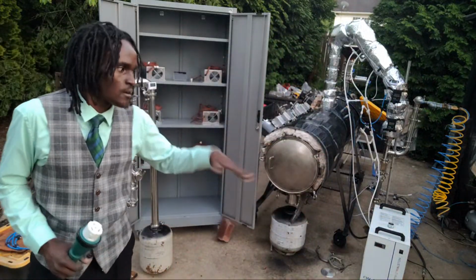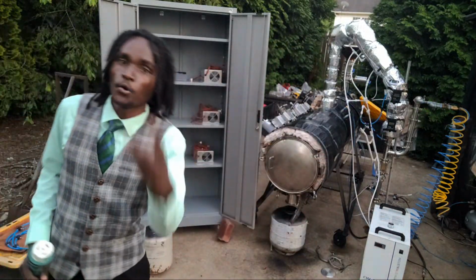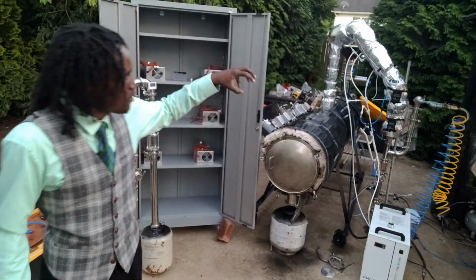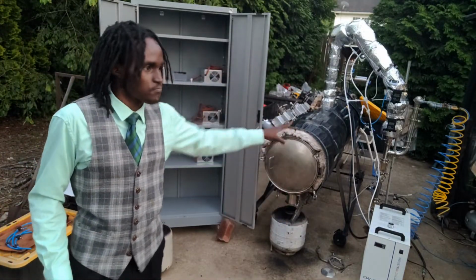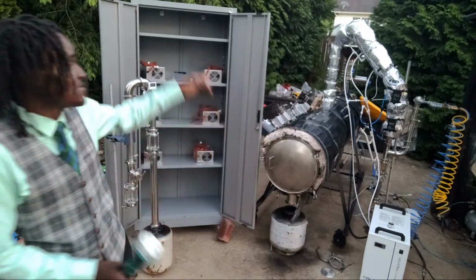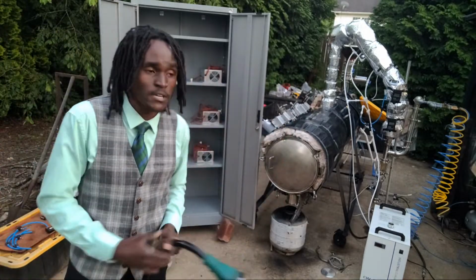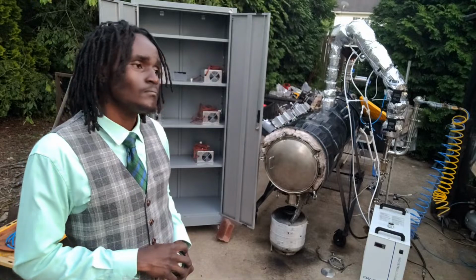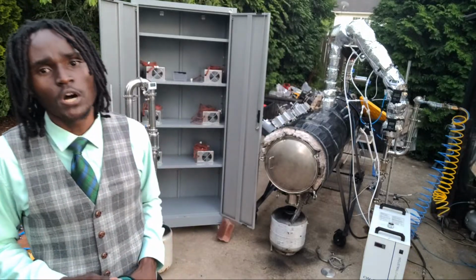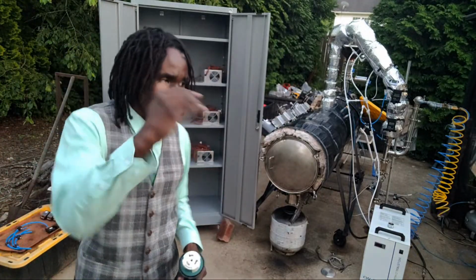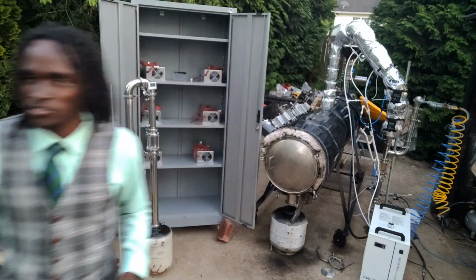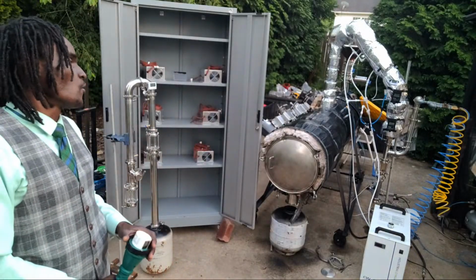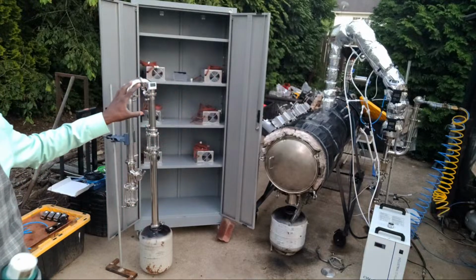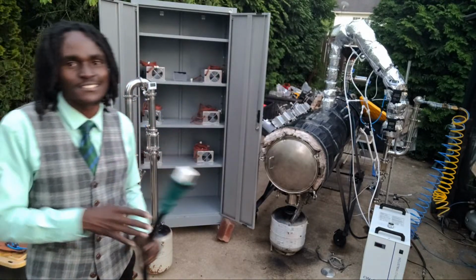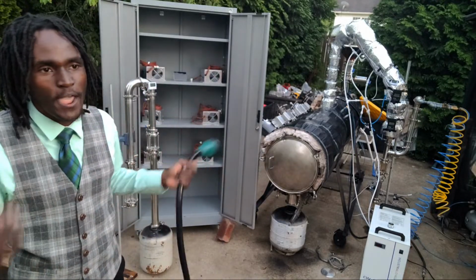But you gotta remember, we have a lot of 120-volt things like the recovery pump, the motor for the blades, the water chiller, and the fans on the machine. They're collectively going to eat up probably like 15 amps, because something that's 120 eats more amps than something that's 220. So I have to limit how many microwave power supplies I can use, because I don't have any leeway above 50 amps.